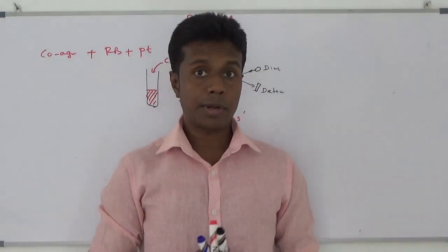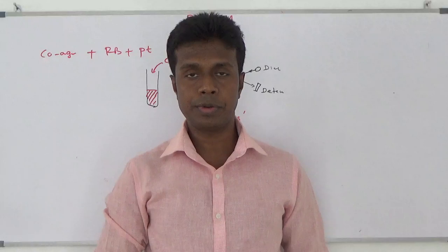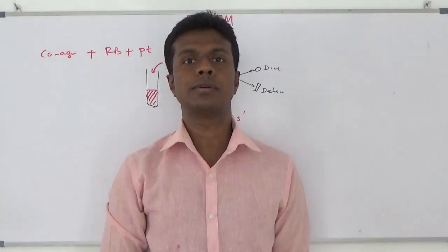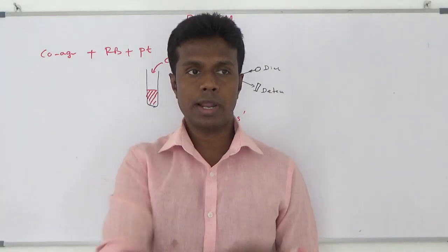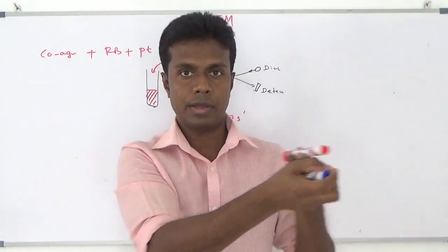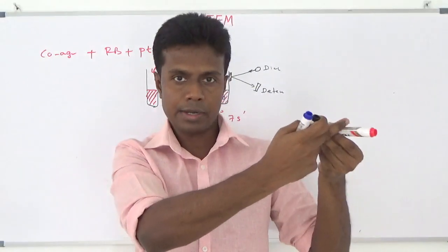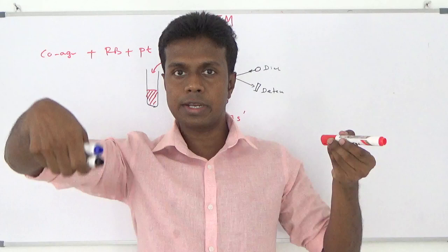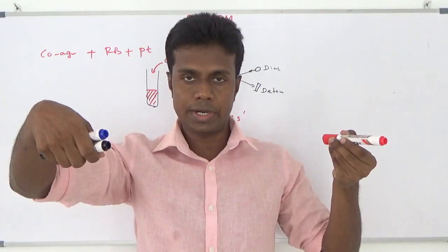For a while, think I am the blood sample containing test tube. He put a pin into my blood sample over my stomach. Then he asked me to rotate, and here is the light emitting diode. The light comes from here and flashes on my chest and reflects back. That reflected part is identified by the photodetector here.